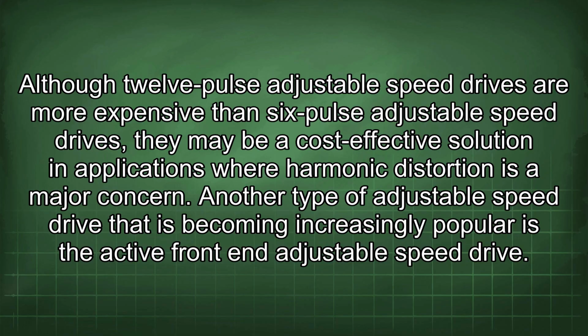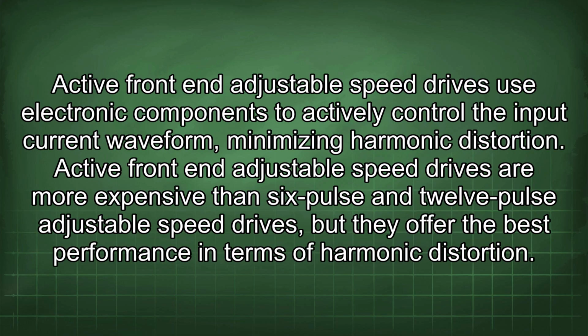Another type of adjustable speed drive that is becoming increasingly popular is the active front-end adjustable speed drive. Active front-end adjustable speed drives use electronic components to actively control the input current waveform, minimizing harmonic distortion. Active front-end adjustable speed drives are more expensive than 6-pulse and 12-pulse adjustable speed drives, but they offer the best performance in terms of harmonic distortion.